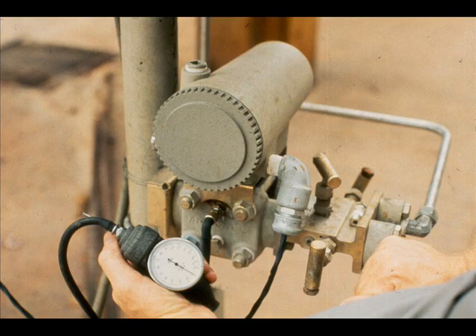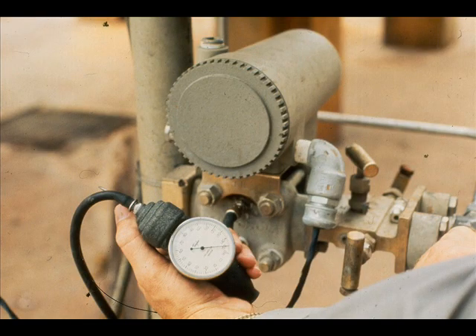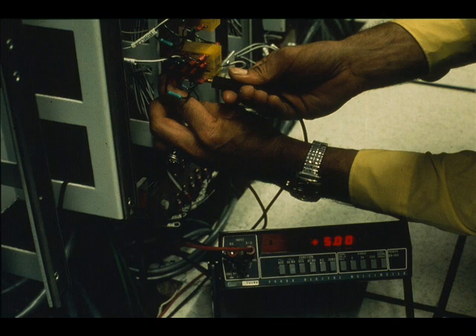With zero pressure differential applied to our transmitter, the digital voltmeter should read the low end of the volt span — here it is 1 volt. With 150 inches applied to the high side of the transmitter, the digital voltmeter should read the high end of the volt span — here it is 5 volts.